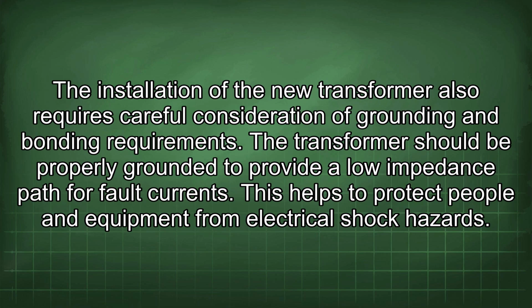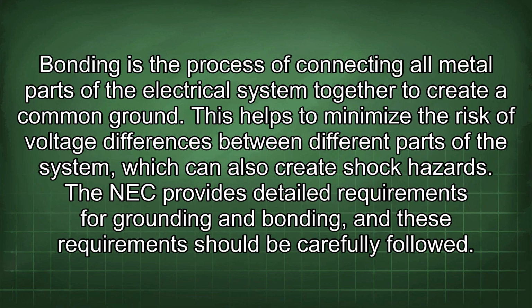The installation of the new transformer also requires careful consideration of grounding and bonding requirements. The transformer should be properly grounded to provide a low impedance path for fault currents. This helps to protect people and equipment from electrical shock hazards. Bonding is the process of connecting all metal parts of the electrical system together to create a common ground. This helps to minimize the risk of voltage differences between different parts of the system, which can also create shock hazards. The NEC provides detailed requirements for grounding and bonding, and these requirements should be carefully followed.